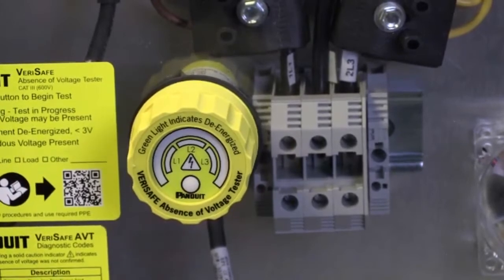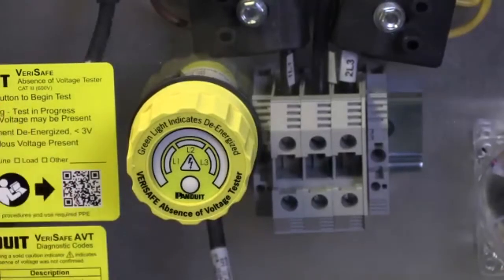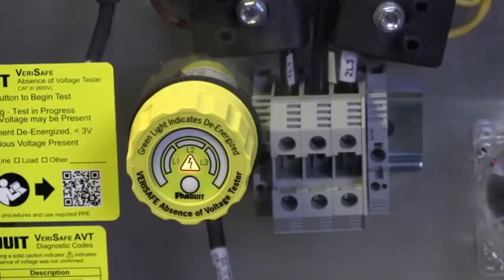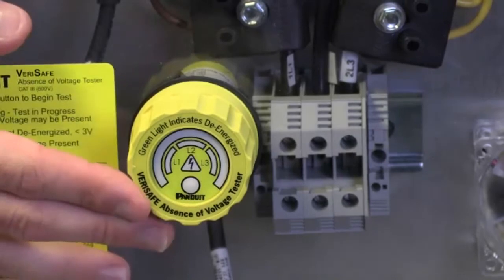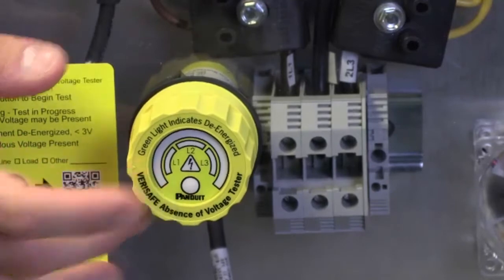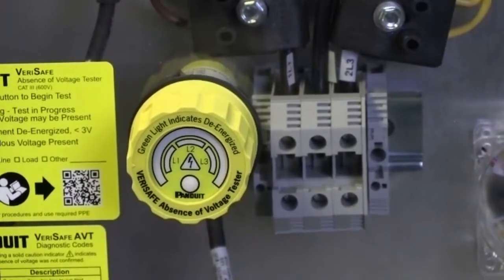The one thing I want to show you guys is what that continuity check does. I flipped the switch down here at the bottom, where I showed you those little toggle switches, simulating becoming disconnected. I'm going to run that same test again. We just got the green LED, but this time it's not giving me the green LED. It's giving me a flash code of 4 flashes, and those 4 flashes tell me I can't verify connectivity inside the system where I'm installed. So it has the intelligence to let you know exactly what's going on, whether it's voltages above 3 volts, firmware or hardware failure, or connectivity issues.